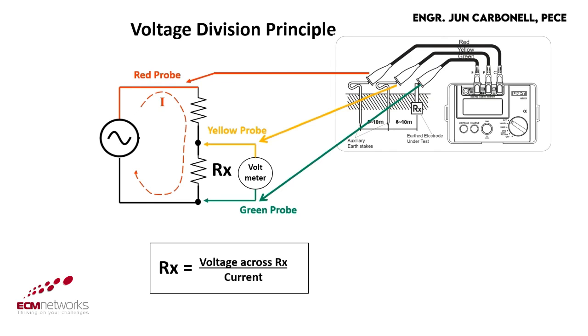Please see the formula. Rx is equal to voltage across Rx divided by the current. If any of the test probes is not properly connected according to the setup, UT521 will not give any resistance result or it will display 0.00. Make sure the clips and auxiliary stake contact points are cleaned for low resistance connection.